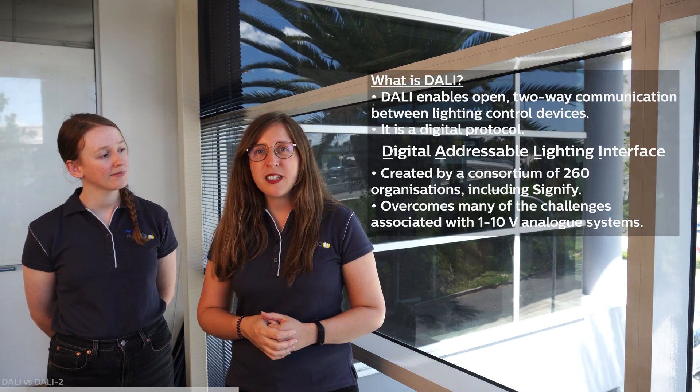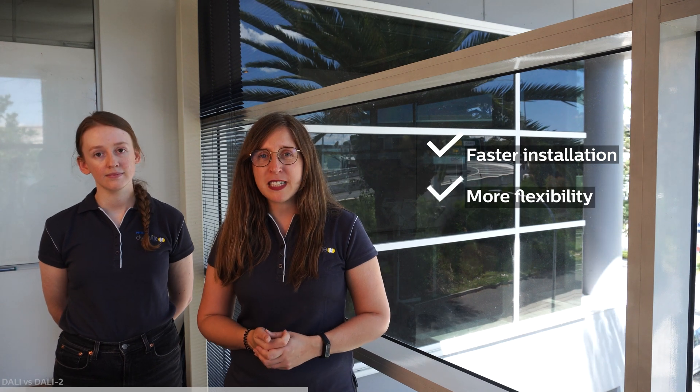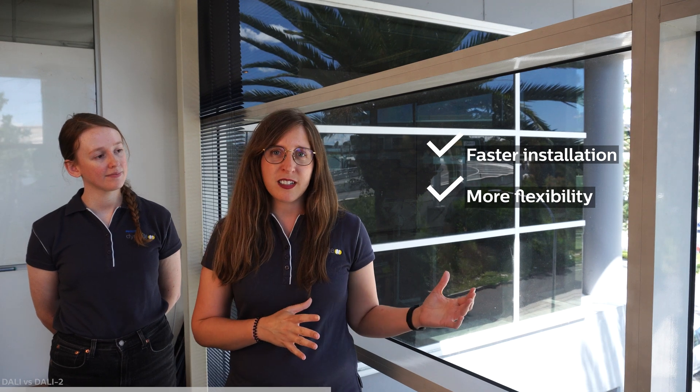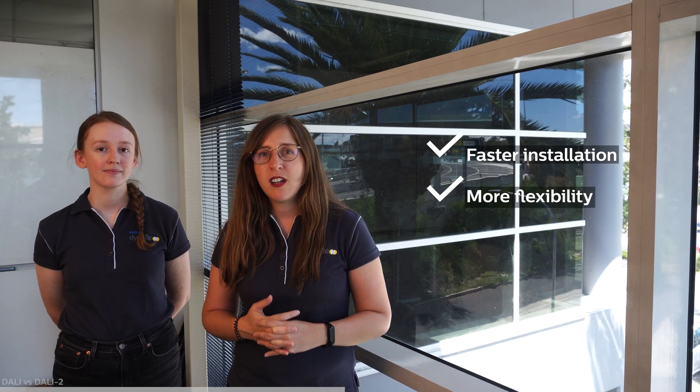It also brings us new advantages, for example, faster installation. Now we have only one pair of cables both for power and data. It's also polarity agnostic so it's quite simple. Also we have a second advantage which is more flexibility and scalability, bringing us not only the broadcast control that 1 to 10 volts has but also addressable control or also group control. So it's quite flexible, for example, if we are going to change the configuration of a room or of a building and the third one was greater control because now with this bi-directional communication we will be able to see the driver status and create some alarms and try to be more efficient with the system.